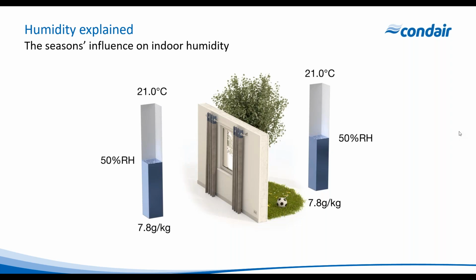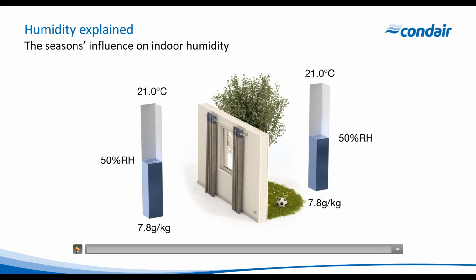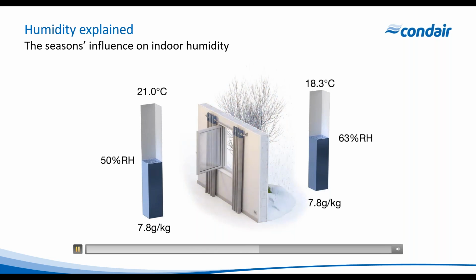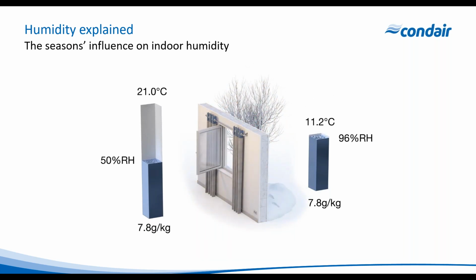So we know that if air travels from one condition to the other, we're still going to be within specification. But let's say that outdoor air starts to decrease its temperature. And this could be either through a season change or indeed it could be between day and night. Well, when the outdoor temperature drops to 10.5 degrees C, the maximum moisture it can hold is 7.8 grams, and it would be at 100% saturate. So if we take that air and bring it into our air at 21 degrees C, we still have enough moisture content or absolute humidity in the air to satisfy the demand of the indoor space.